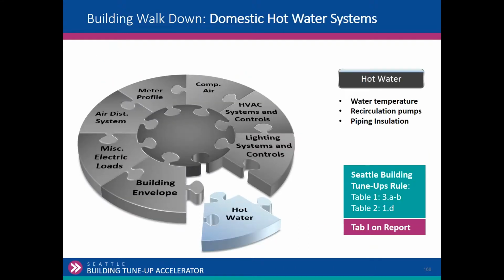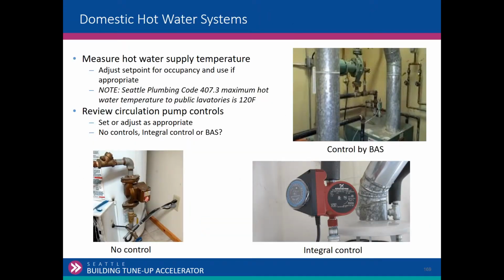Hot water, domestic hot water side. Most of their buildings are going to have domestic hot water systems, if not just for lavatories, janitor closets, that type of thing. Process water, so restaurants, and there are some exclusions for those types of things, they're outside the scope of this. So we're primarily talking about service water, not process water. There's a couple of things to emphasize. One is hot water temperature. Is it appropriate? If it's a public lav, is it 115 degrees, or is there a mixing valve? Is the mixing valve temperature appropriate? Use your judgment on that.